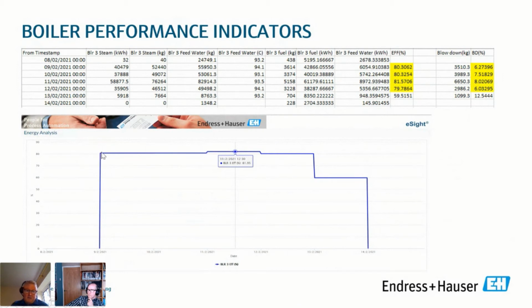You won't get, if you instrument a boiler correctly, even if you're using an economiser on a steam boiler, more than 84% for the fuel to steam efficiency, just because of the losses in the system. So if you're suddenly doing the calculations and finding you've got 90%, there's usually a problem somewhere in the units or the measurement. It looks too good. And conversely, if you're down at 40%, there's something wrong there.